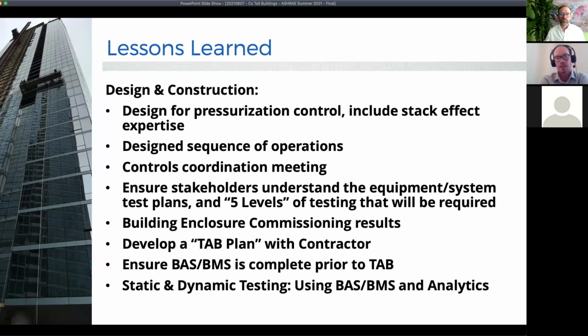And if it's a leak down in the vestibule or in the lobby versus a leak in the penthouse, those have different effects on stack. But again, having a tight building is important, and testing to ensure that it is tight is a part of that commissioning process.